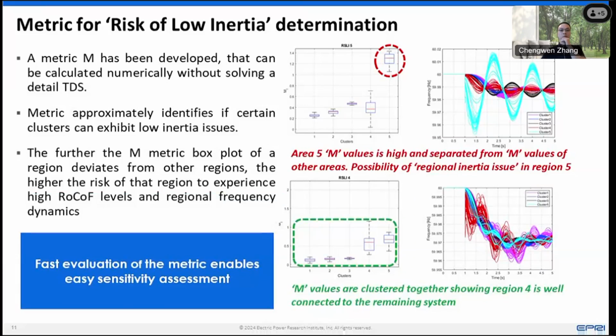The way to read this box plot is: if a region's box is way higher than the rest of the system, that's an indication of high risk of regional dynamic issues. If you run time domain simulations for cluster 5, at the bottom of the Texas system, you can see these light blue curves — those are frequencies measured in cluster 5. It deviates far away from the rest of the system.